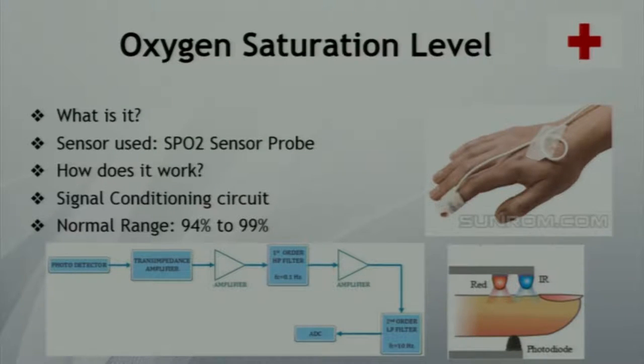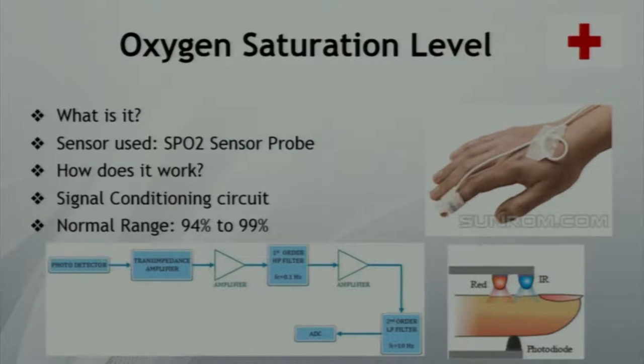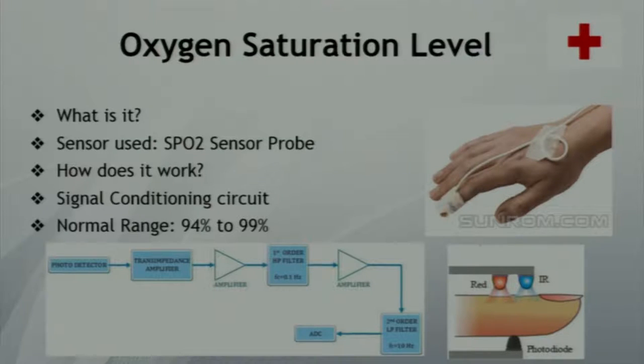Oxygen saturation level is the concentration of oxygen in the blood. The sensor we used was a SpO2 sensor probe, worn around the finger. It emits light of two different wavelengths — red light and IR light. The transmitted light is absorbed by a photodiode and converted to current. The oxygen saturation level is calculated as the concentration of oxygenated hemoglobin divided by the total concentration of hemoglobin in the blood.